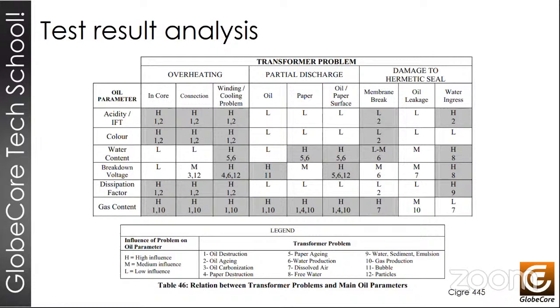So we already have a method which allows us to link the tests we usually run and connect them to corrective maintenance. Usually, whenever we talk about maintenance of a transformer, we focus on preventive maintenance, which mostly just involves testing. And in many cases, we are good at preventive maintenance, but we don't often take corrective action. So this presentation is meant to help a little with the corrective processes when we already have a problem and need to do something about it. So as we will see, this type of corrective maintenance is often a step that we do not take. In some cases, there's also a fear of decision making. And as this corrective service usually has something that all companies fear, and that would be the planned shutdowns. And these scheduled shutdowns must be performed after preventive checks give us the indications that we need to correct operation of the transformer. Next, please.